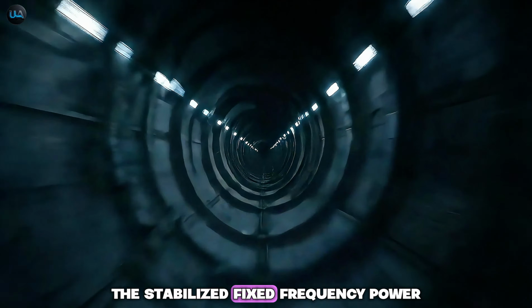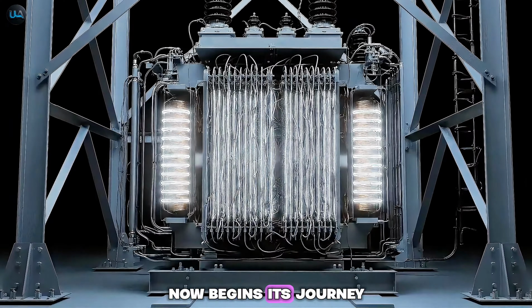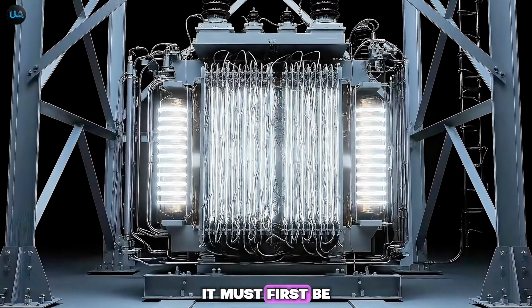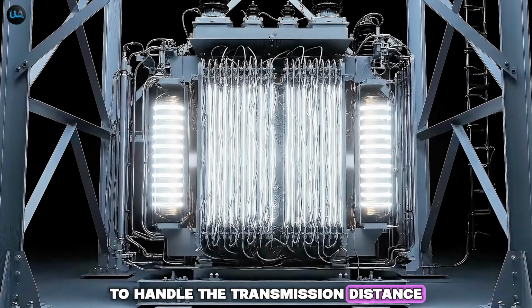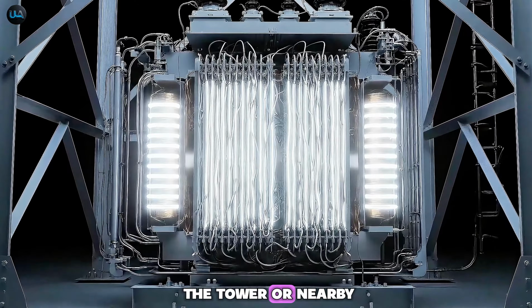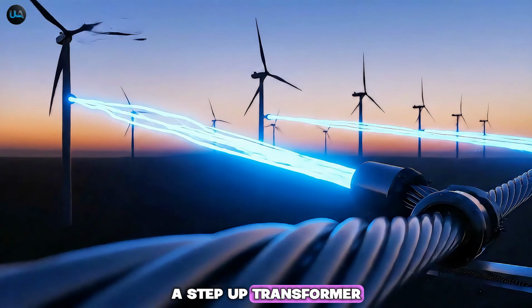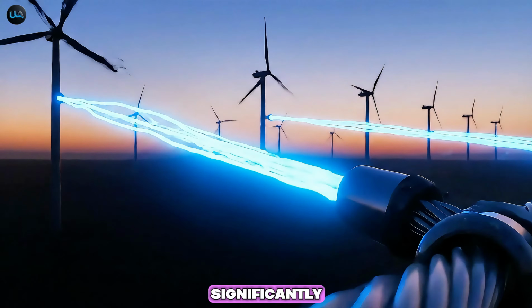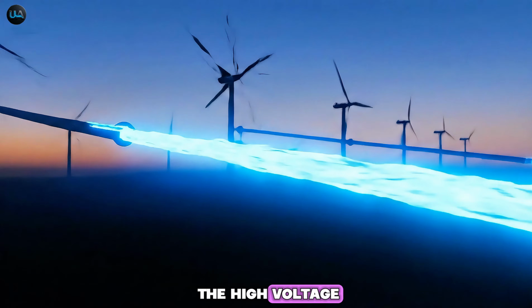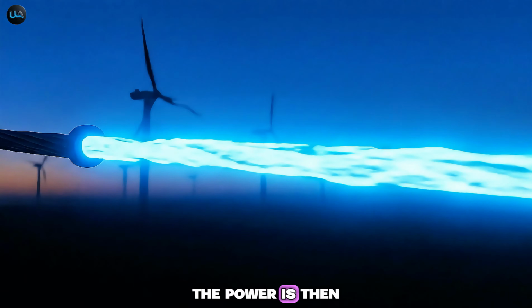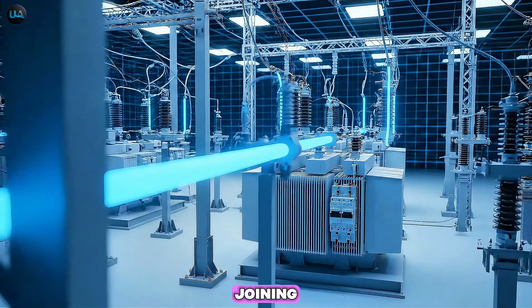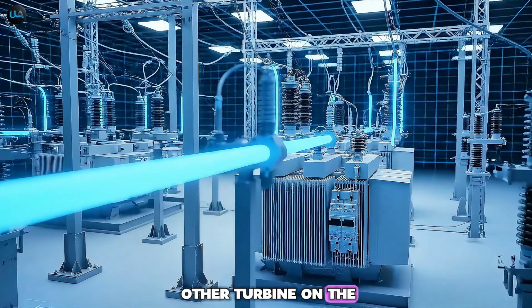The stabilized, fixed-frequency power now begins its journey down the tower. It must first be stepped up to handle the transmission distance. At the base of the tower or nearby, a step-up transformer increases the voltage significantly, preparing the electricity for the high-voltage collector lines. The power is then routed through a collection network, joining the output of every other turbine on the wind farm.